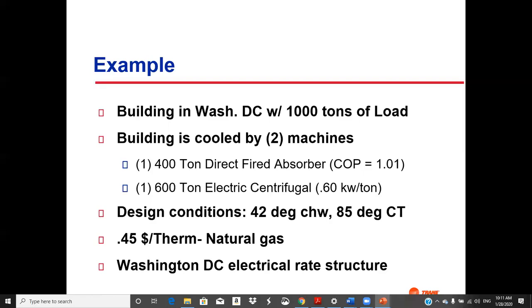Design conditions, 42-degree leaving chill water temperature. That's a pretty standard number. Someplace between 42 and 45 is what you're going to need to see, especially in a humid climate. If this creeps up too much, the water's not cold enough in the coils and the air handler to condense out the moisture in the space, and you lose humidity control. So in a drier climate, you can provide pretty good sensible cooling with warmer temperatures. But in Tennessee, the eastern part of the US, in the summertime when there's humidity load, you're going to have 42 to 45 degrees.